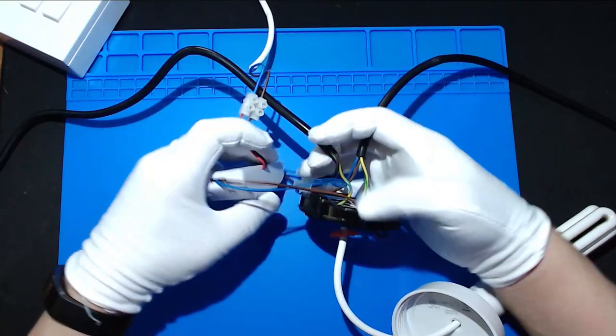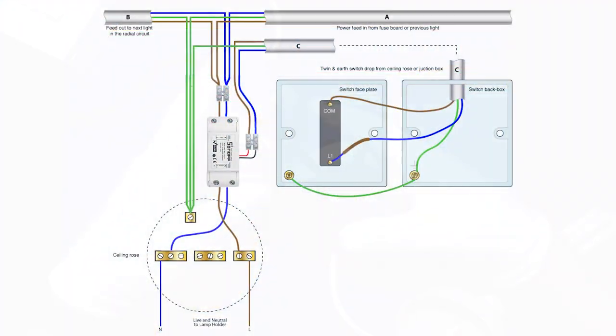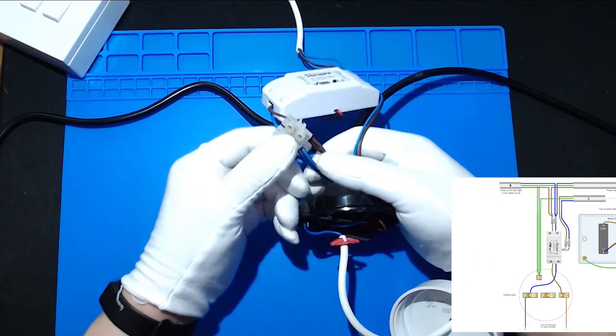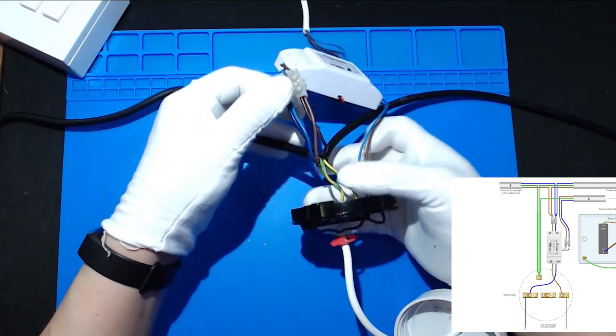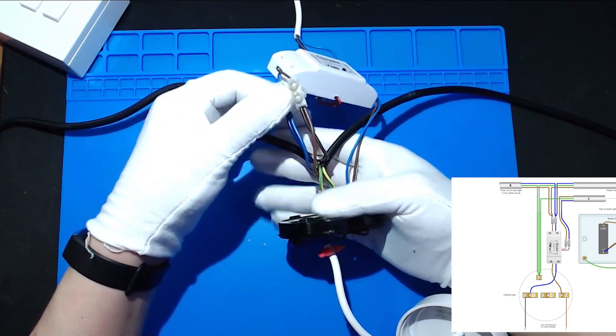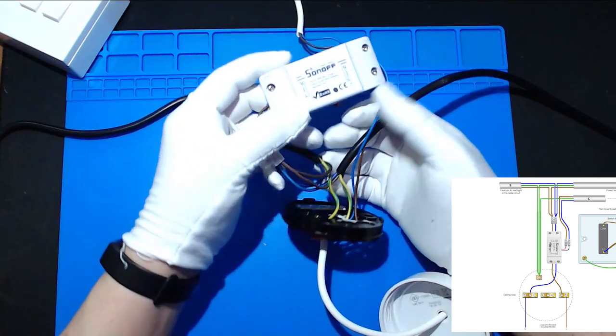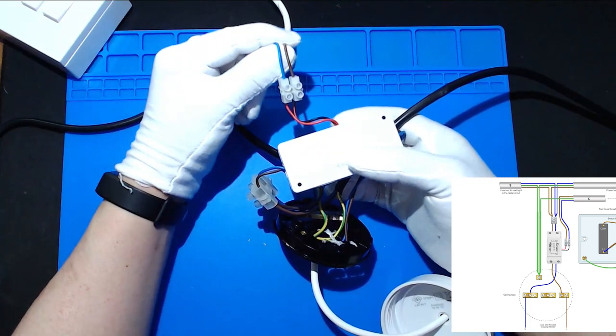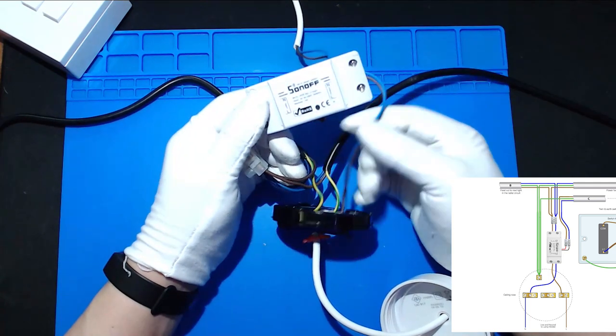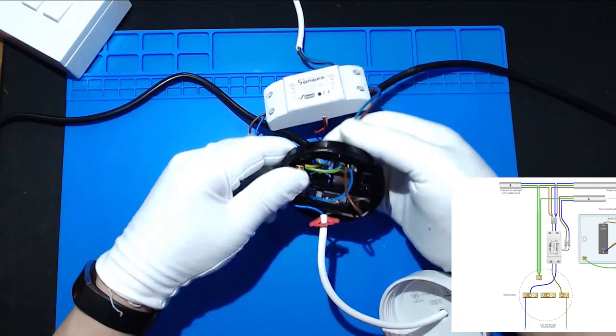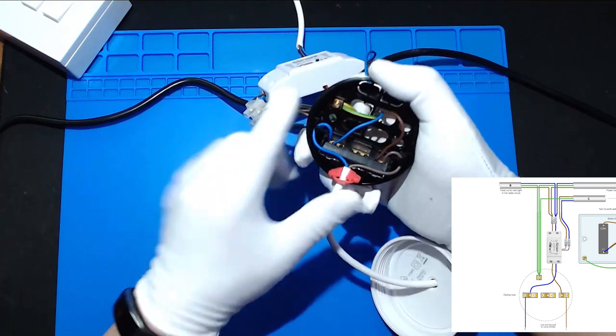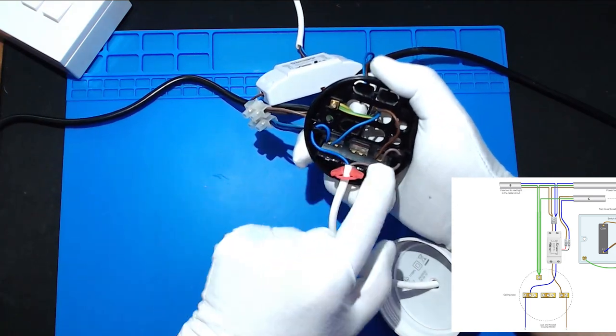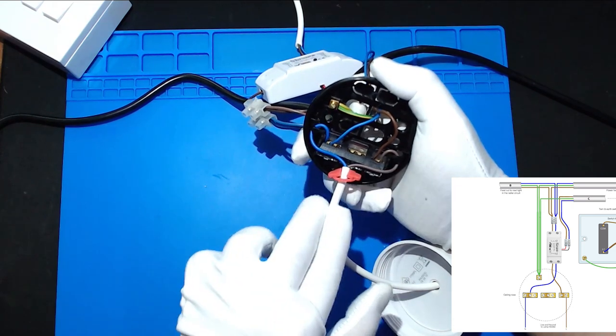In the ceiling you'll have your ring in and your ring out connected to the two blocks there and see that coming out like earths there. And then your switch is connected to that little block that we put on the side. And then the two wires from the output come back through the ceiling through the back of the rose.